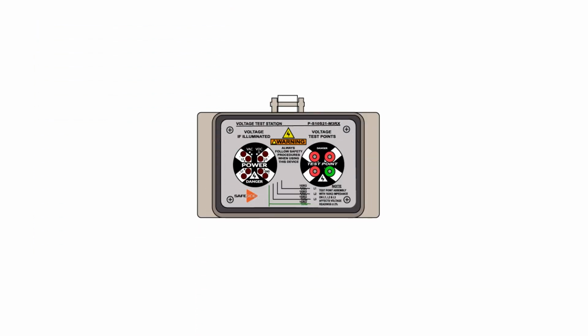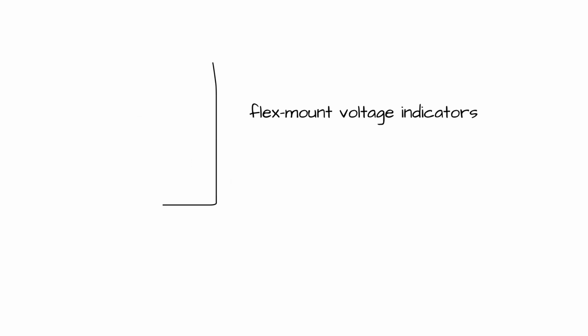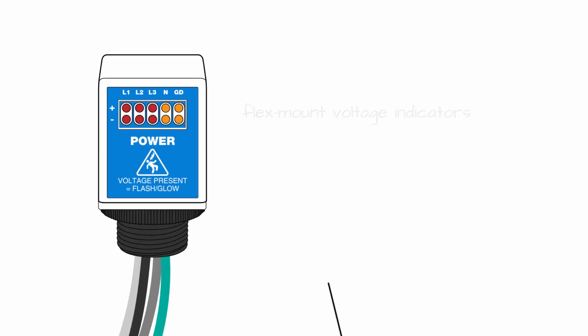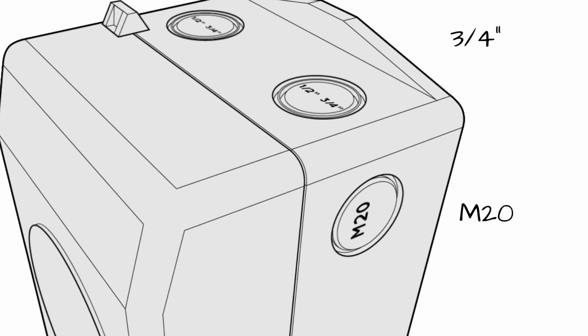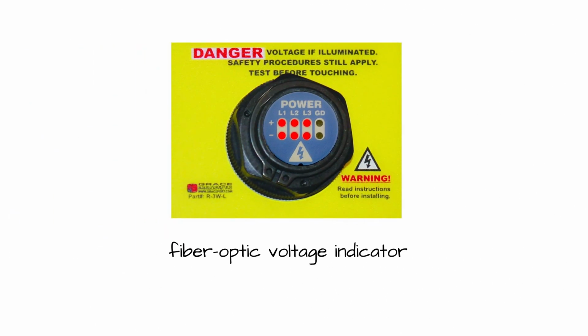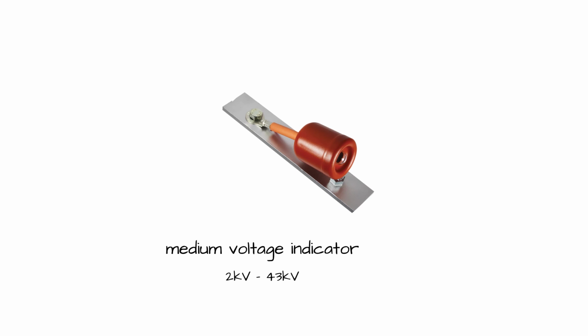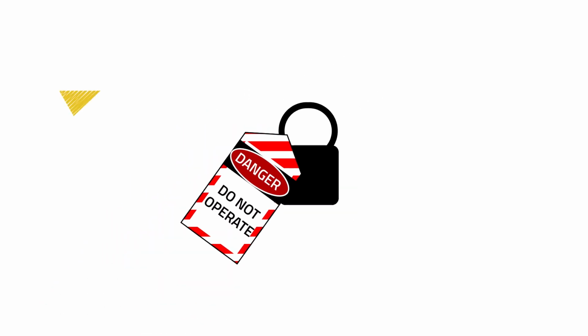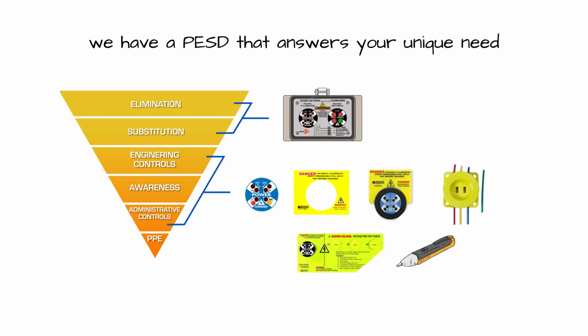Voltage Test Station is another form of PESD that combines a voltage indicator and safe test points in UL-recognized lockable housings with Type 4, 4X, and 12 ratings. Other PESD product variations include flex mount voltage indicators that can mount onto any electrical enclosure with a 3/4 inch or M20 conduit knockout, a fiber optic voltage indicator for use in dead front bus panels with no voltage to the door, and a medium voltage indicator that can bolt directly to the bus bars from 2 kV through 43 kV systems. No matter how simple or complex your lockout-tagout procedure is, we have a PESD that answers your unique need.